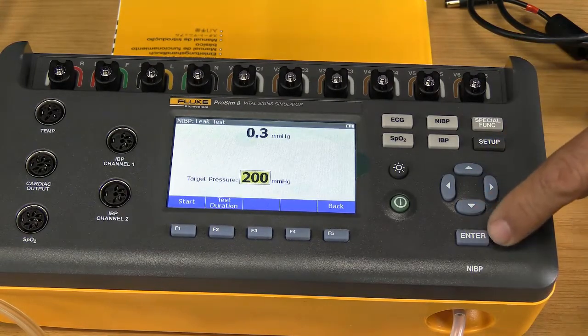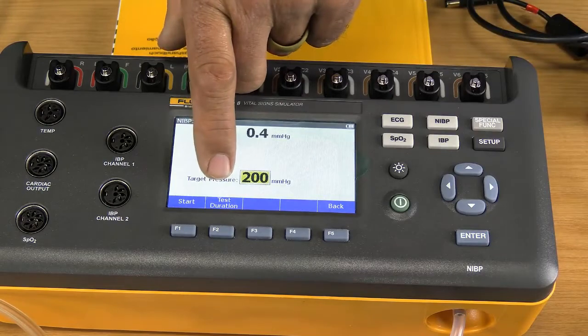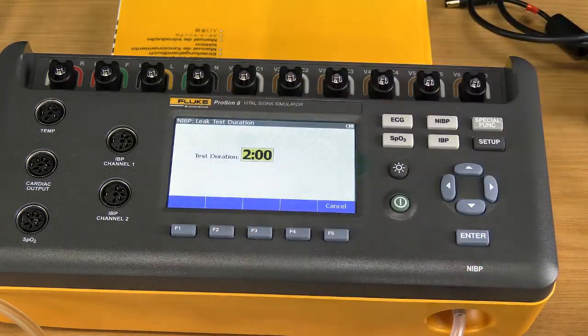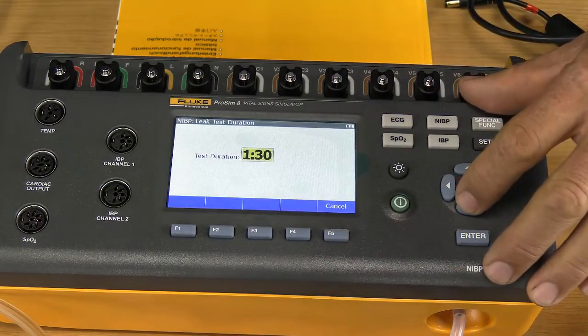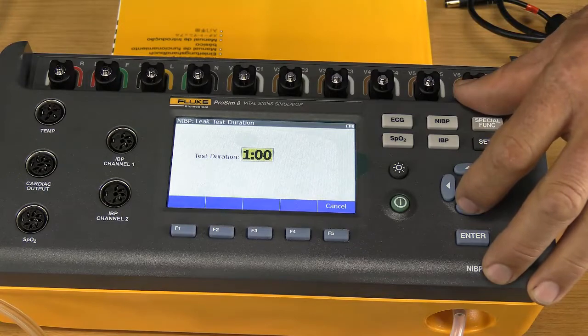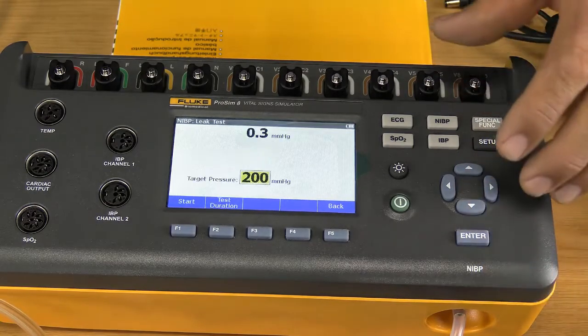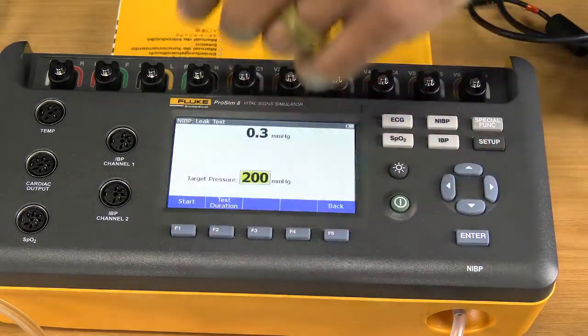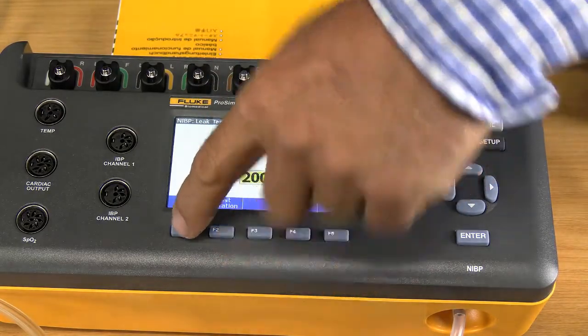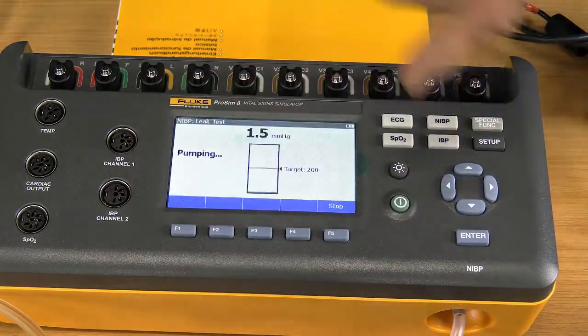Then I press enter, and then I've got a second button here, function 2, which says test duration. So I'm going to pressurize the system, and then I want to close the system for a certain period of time, and then measure what the pressure drop during that time was. So in my case, or in the case of the Philips monitor, we make use of a 1 minute duration. I say enter, and then on the machine, I press the start button.